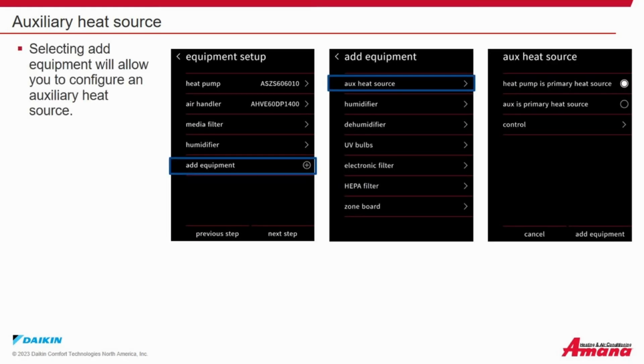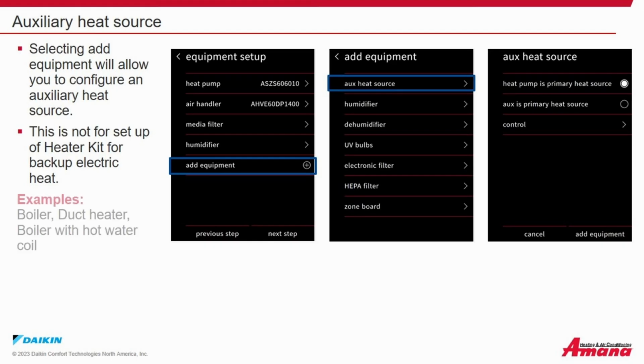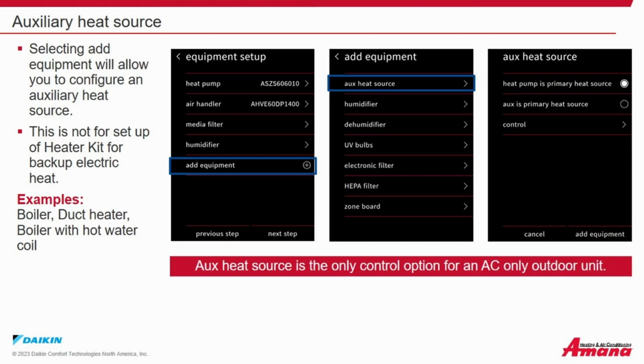Auxiliary heat source. On an Amana Smart Thermostat, selecting Add Equipment will allow you to configure an auxiliary heat source. This is not for setup of heater kit for backup electric heat. Your examples of auxiliary heat would be boilers, duct heater, boiler with hot water coil. Auxiliary heat is the only control option for a cooling-only outdoor unit.